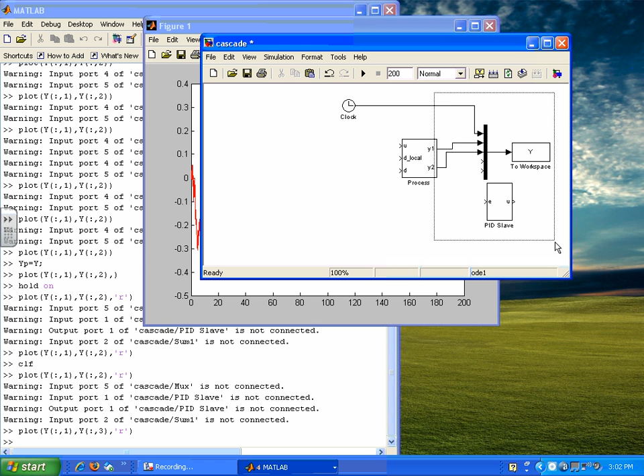See, there is a disturbance and then there is a local disturbance. Local disturbance affects the slave loop, D affects the primary loop. That's how it is. D local is added to this Y2. D is added to Y1, right? So what you should also be doing is, given a step to the local disturbance, if you had the cascade control system in there, how does the primary variable respond? If you did not have the cascade control system in there, how does Y1 respond? And what you should find is that local disturbance by the action of the slave controller gets removed. So there is not much of an effect on Y1.